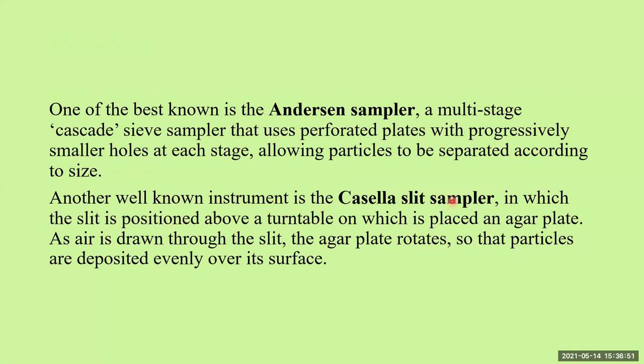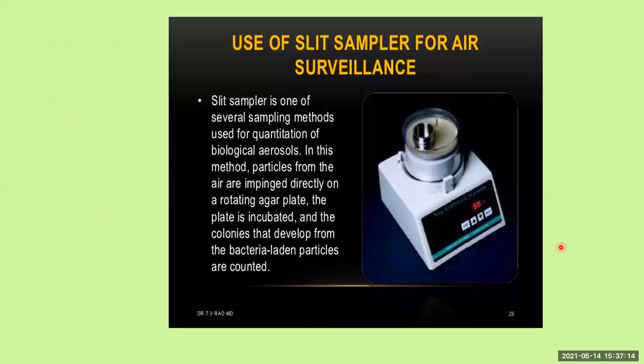Another well-known instrument is the Casella slit sampler, in which there is a slit positioned above a turntable on which an agar plate is placed. Air is drawn with the help of a sampler and enters through the slit. As the agar plate rotates on the turntable, particles are deposited evenly on the surface of the agar.